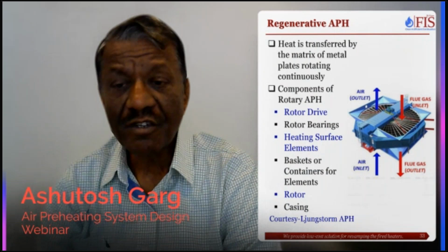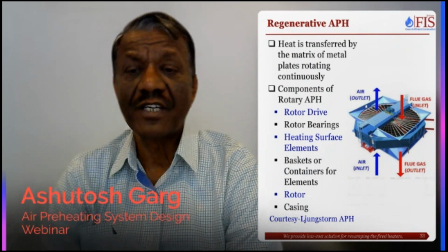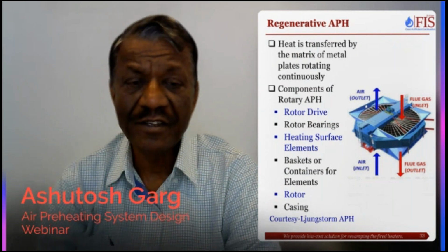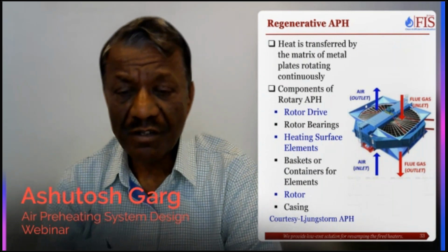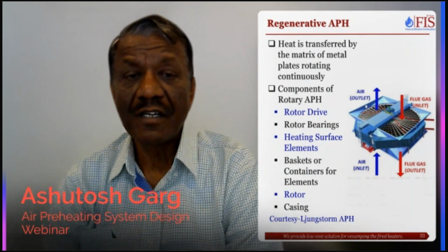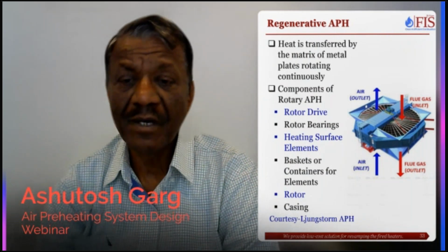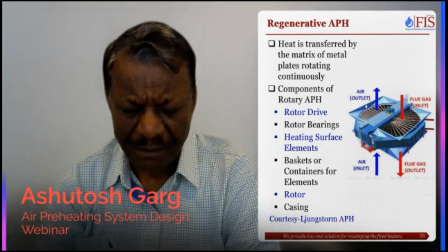And there it is out of necessity because the volumes are such that if you go with a recuperative air preheater, the cost and the size will be tremendous. So because of those reasons, a rotary air preheater is the de facto standard in the power industry. And here the concept is very simple.